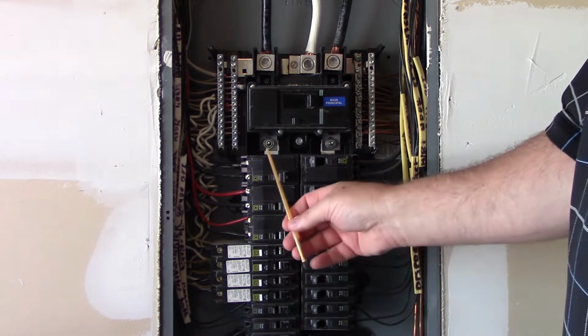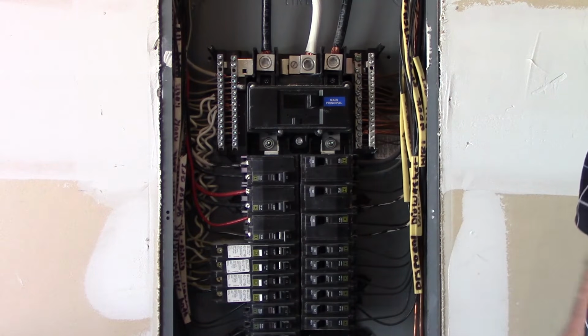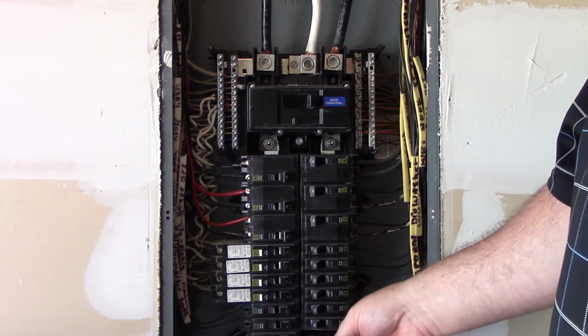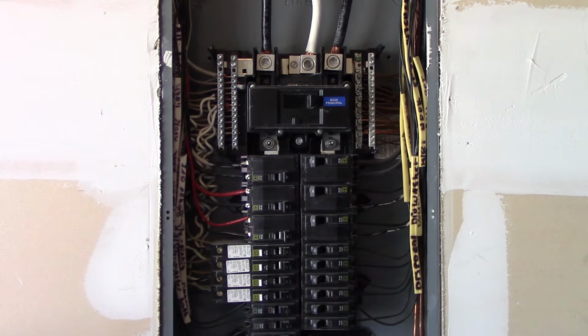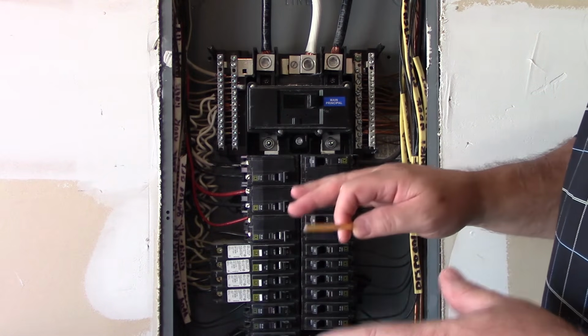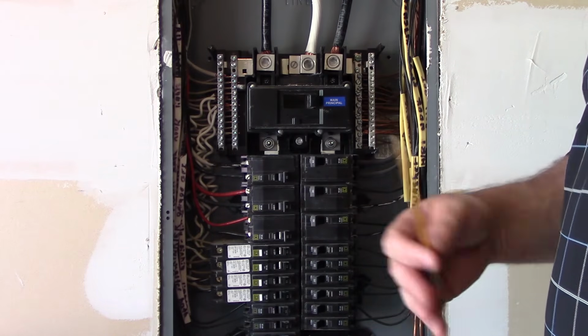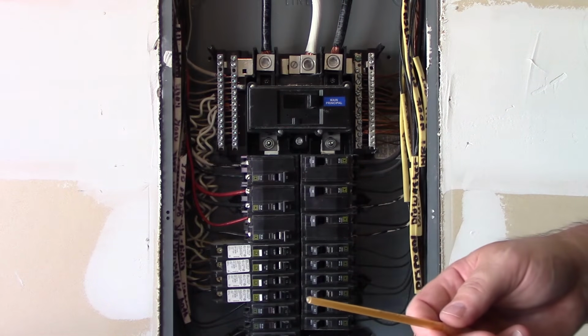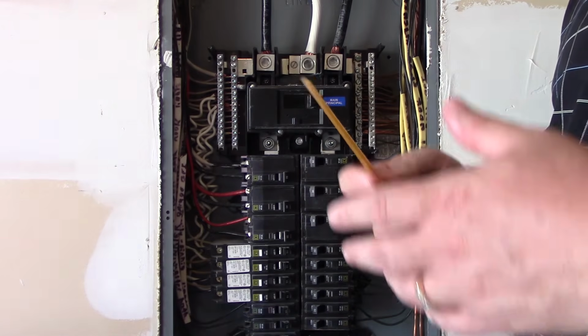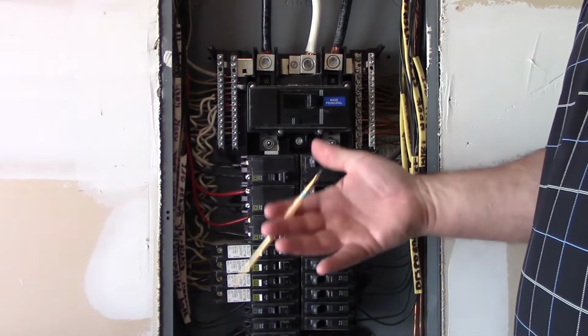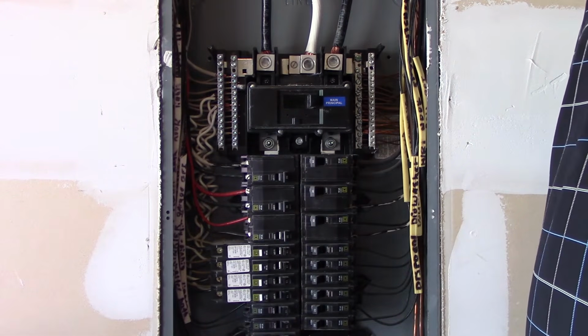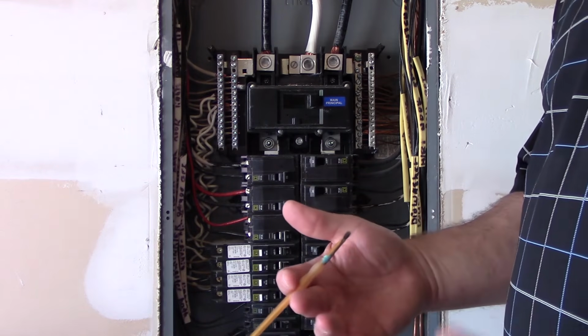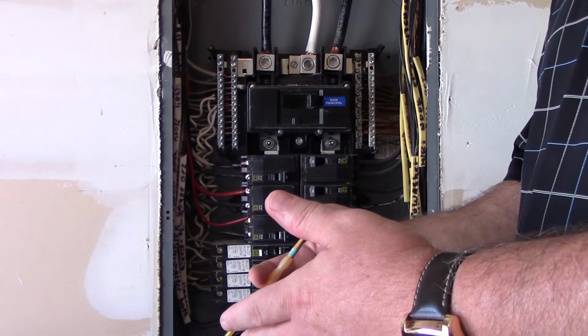Now, another thing we're looking at, these are all Square D breakers. If I happen to see another brand in here, one thing I have to realize is that this panel recommends the use of Square D products. However, they do make certain breakers out there that are called classified, that have been identified and evaluated for use in other manufacturers' enclosures. Okay, so it doesn't void any warranty on a replacement because of the Magnuson-Moss Act.